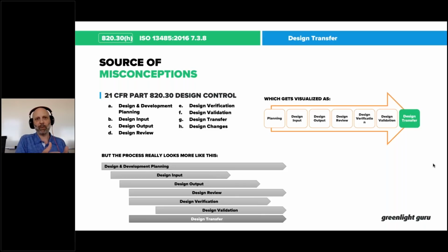I talked about design outputs being the recipe for your product, and that eventually the design outputs will become what's known as the device master record. Well, that's a design transfer concept: I'm establishing the recipe for my product. I'm calling them design outputs. That's an element of design transfer. When I get into verification and I'm building units for testing and analysis purposes, I'm basically following that recipe to build specific units. Well, that is a level of manufacturing that's involved at that point. So there's design transfer that's involved there.